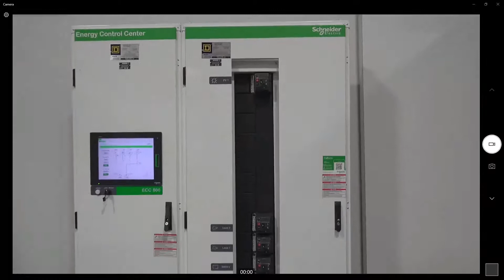There's some logic set up that says, if the utility drops out, let's go to generator. If solar is available, let's utilize solar along with the generator to supplement it. If we're at night and there is no solar and we're in a heavy load situation, let's utilize battery backup to supplement the generator. And if the battery runs out, then let's do some load shedding and drop off our non-critical loads and keep our critical loads on the generator. There's a lot of logic that can be built into this, but essentially it utilizes power in the most effective way possible, both from an efficiency standpoint and a reliability standpoint.